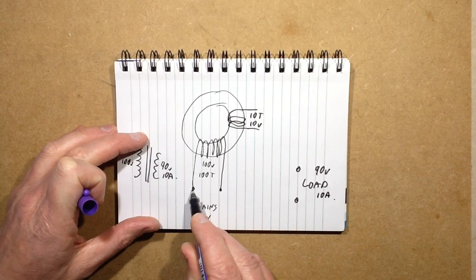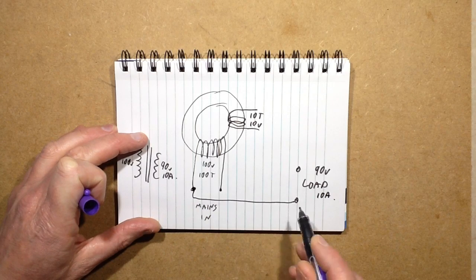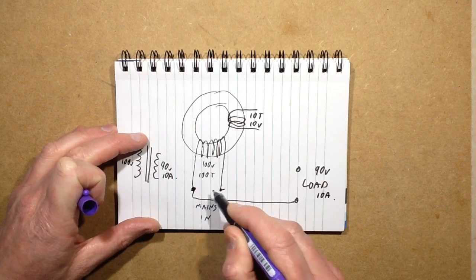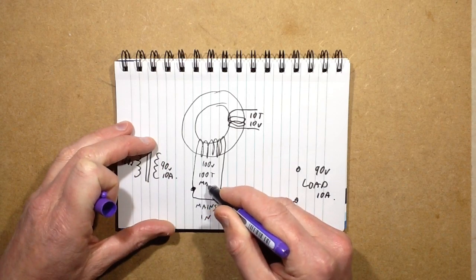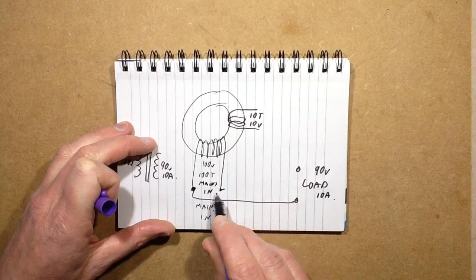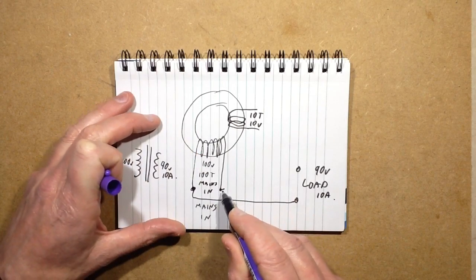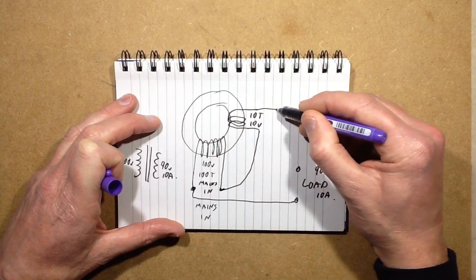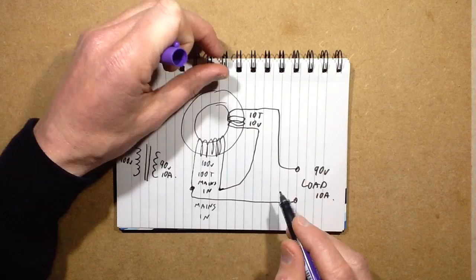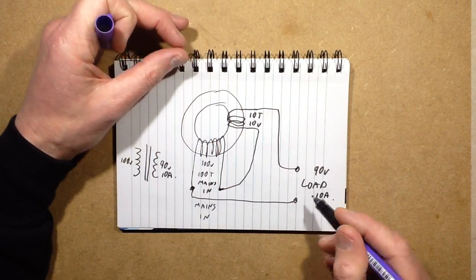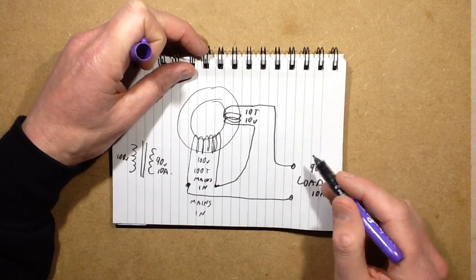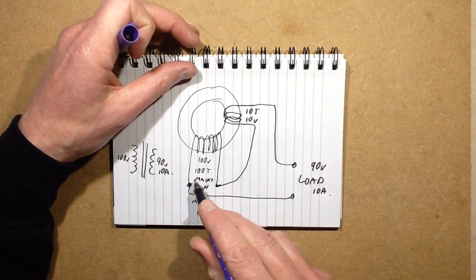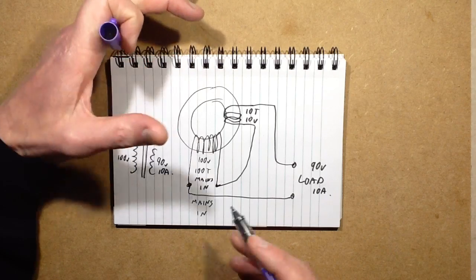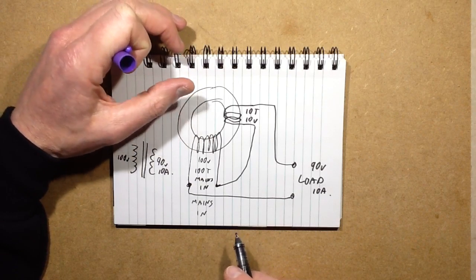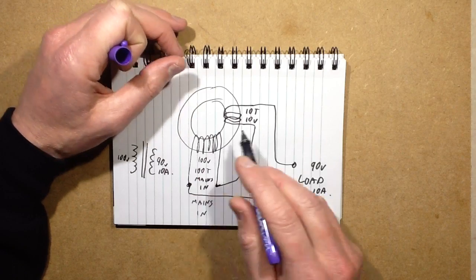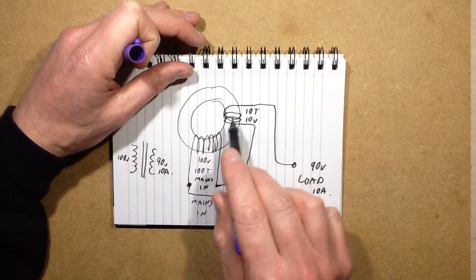We take one connection from the main supply, goes straight to that. The other connection from the main supply, because this is, I'll write mains in. The other connection doesn't go to the load. If it went to the load it would be seeing 100 volts. Instead, it goes via this winding. And then it goes to the load. And that winding is effectively in series with the load. And depending on the polarity that you put that winding, it will either increase the voltage by 10 volts to 110 volts, or it will drop it by 10 volts to 90 volts from this original 100 volts. And obviously this can apply to 120 volts, it can apply to 240 volts, even industrial supplies, 600 volt supplies, you could apply the same technology as long as it's AC, because the transformers require AC to couple through.